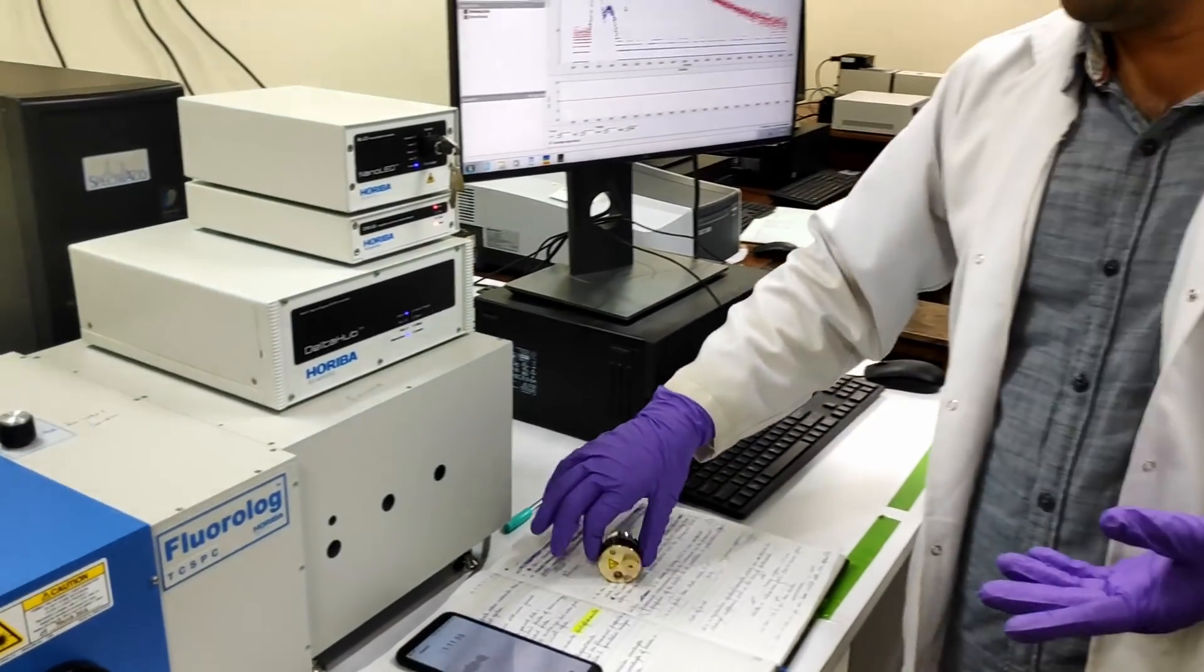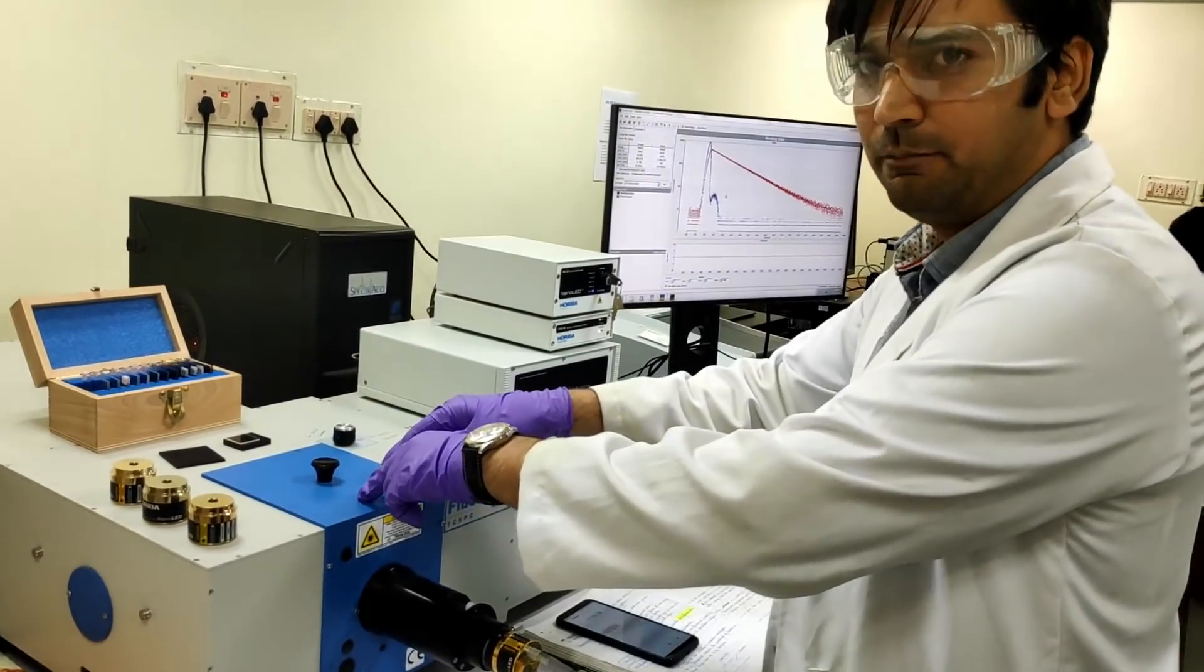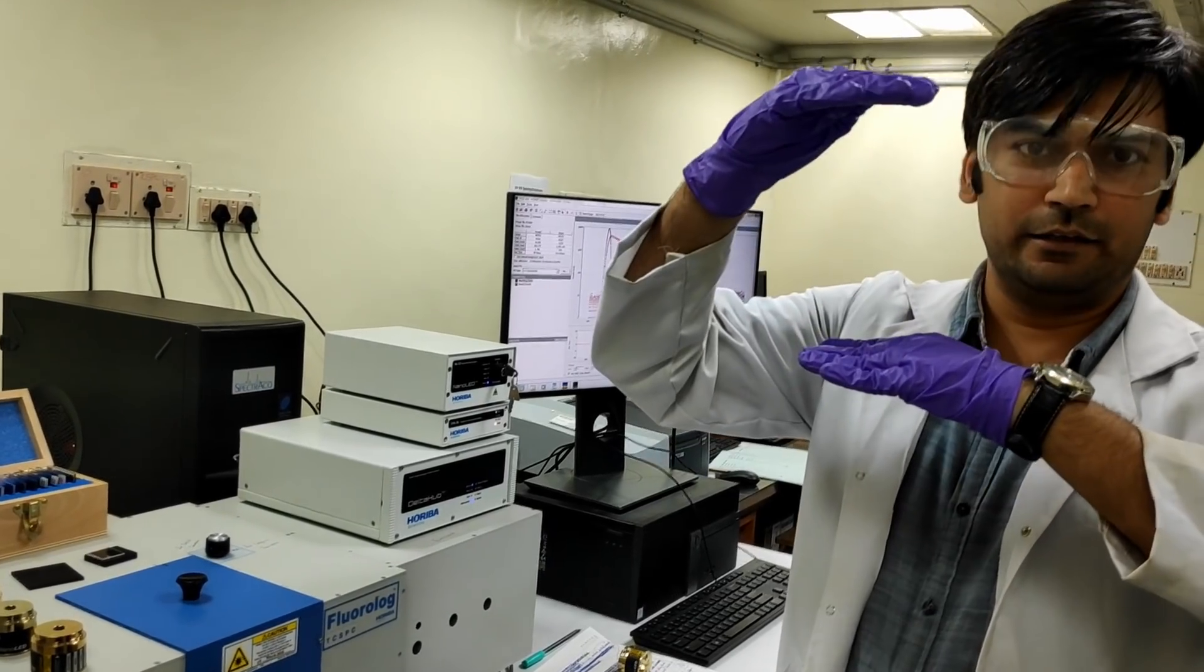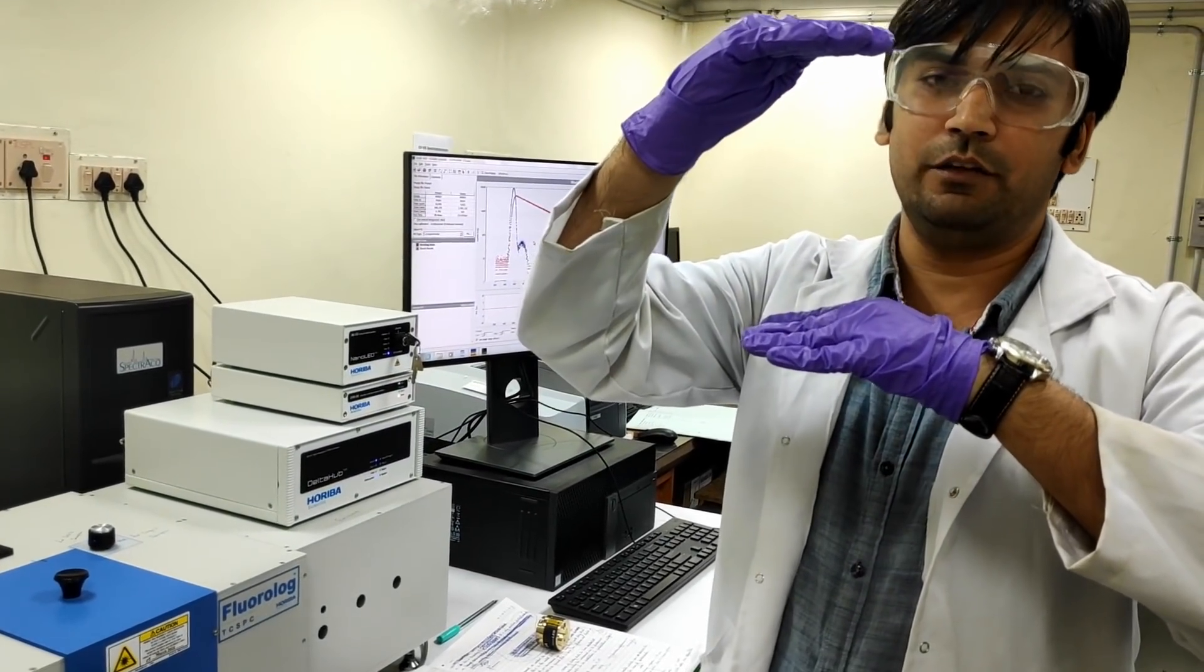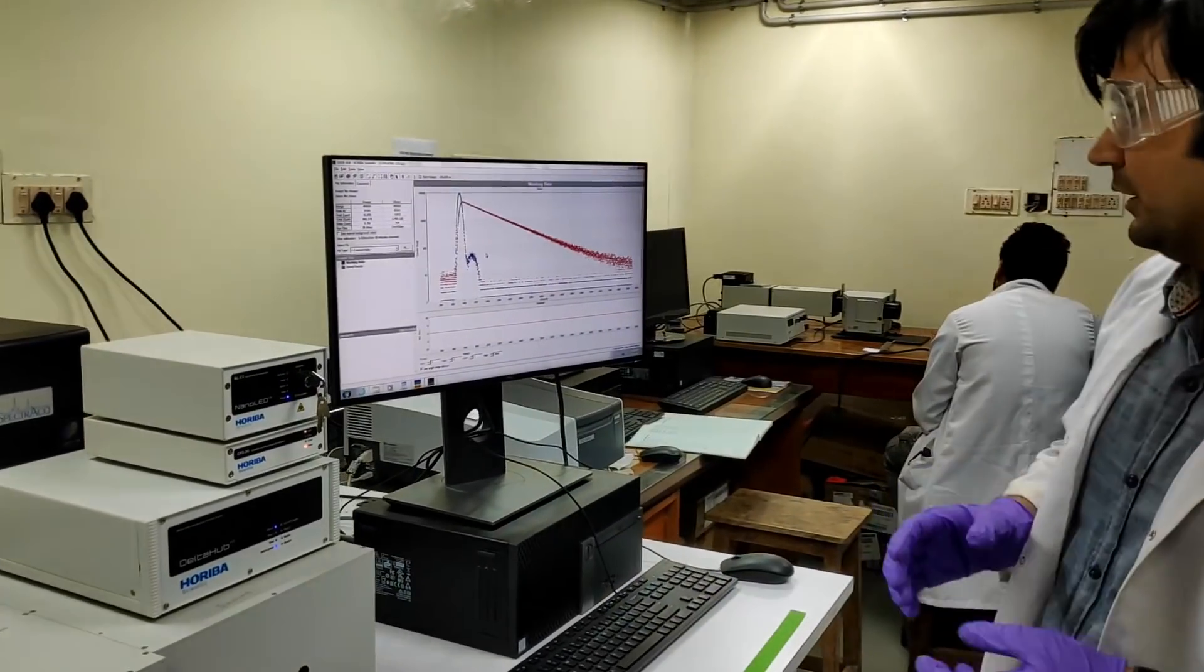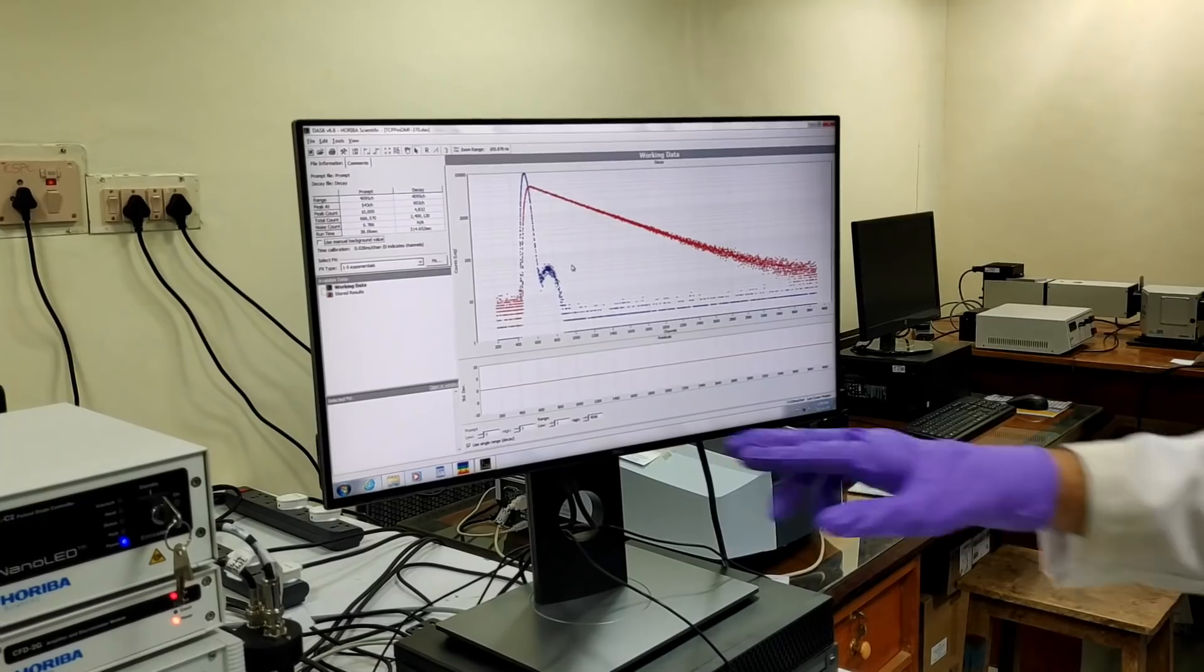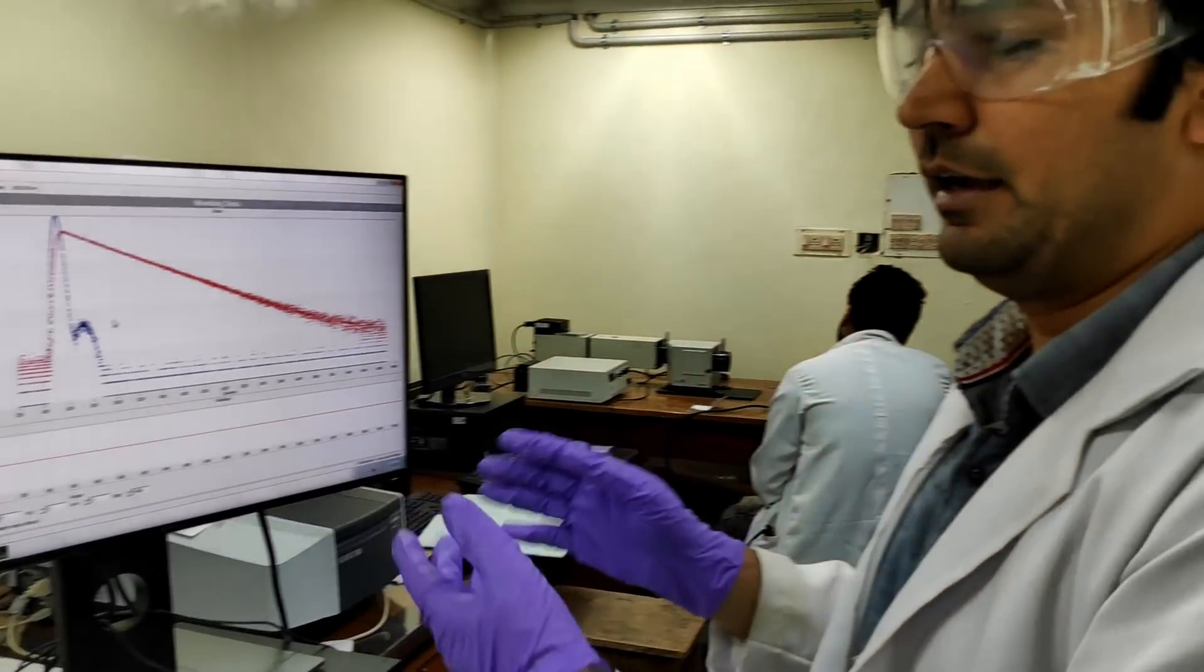We also have filters to cut the wavelength and the intensity of the light reaching to the detector. So talking about the working principle, we incident the monochromatic light on the sample, which will jump the electron from the ground state to the excited state. So this equipment measures for how long the electron will stay in the excited state before coming back to the ground state and emit the fluorescent light. This is how we get our excited electron decay data for any specific material that we are analyzing.